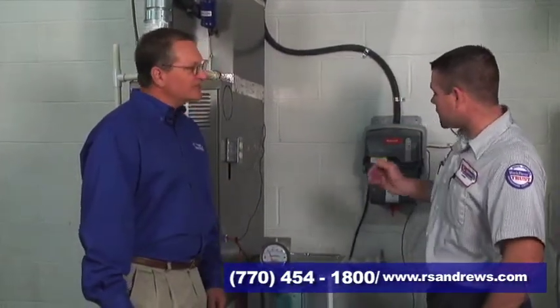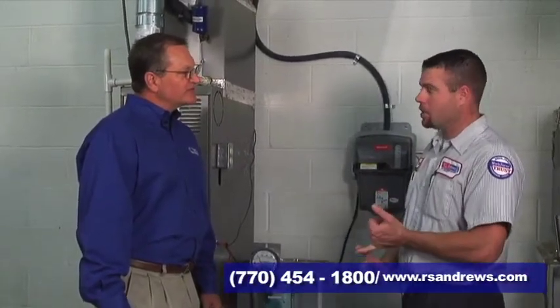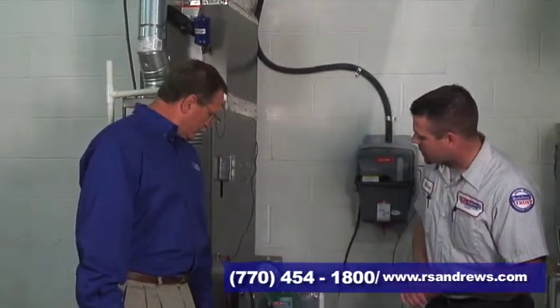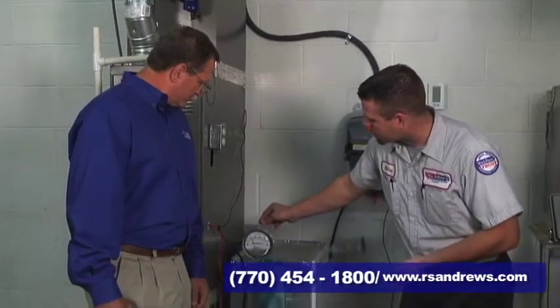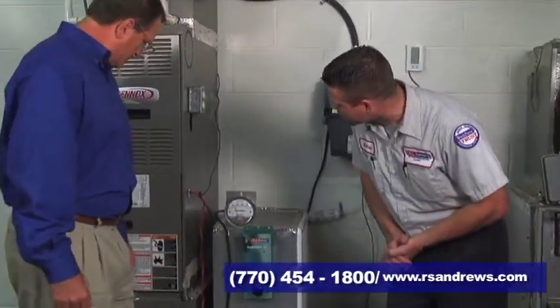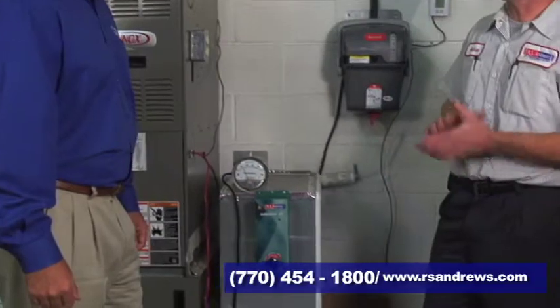What I'd like to simulate for you now is actually the ductwork either being A, collapsed, or B, the filter not being changed out. I want to show you the effect that it has on your system. Right here, this is a Magnehelic gauge, and it's showing how much static pressure is in the system. Right now, I'm just under 0.3 of an inch on the water column.